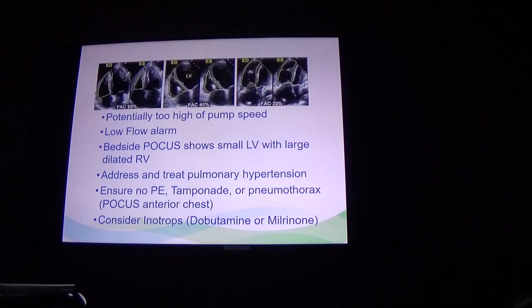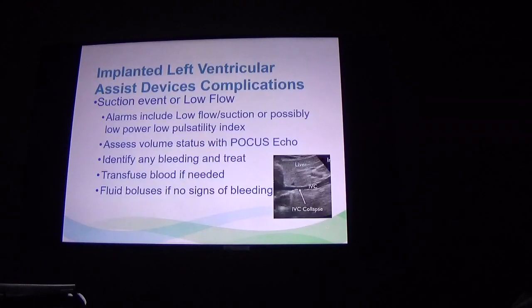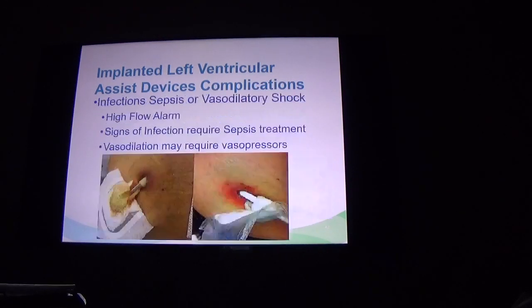And consider vasopressors. So here you have a nice normal little RV, and over here it's really dilated and not squeezing, and a tiny little LV. So that's probably a problem with right ventricular failure. With a suction event or a low flow event, you're going to get an alarm that says low flow and possibly low power or low pulsatility index. Assess the volume status, see how they look. Are they bleeding from anywhere? Stop that bleeding. Transfuse or give fluids as needed. And that's how you're going to fix that problem.